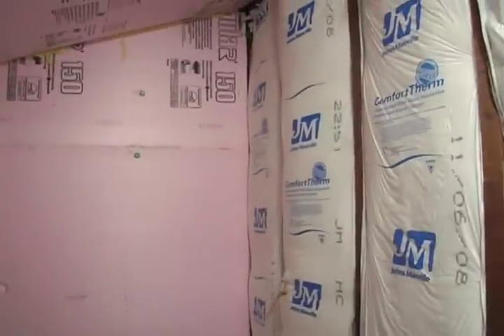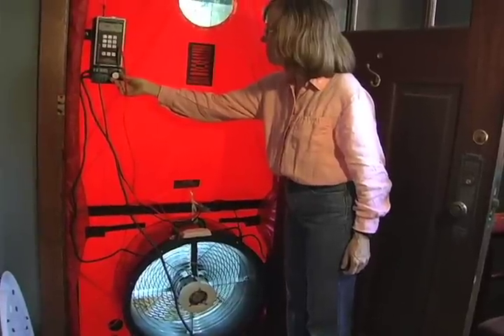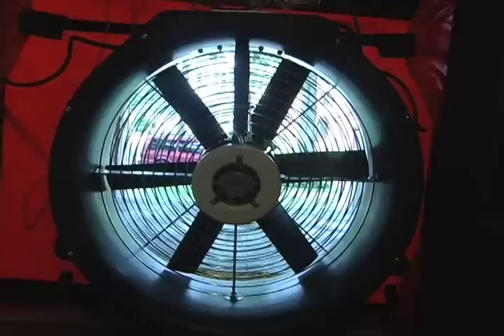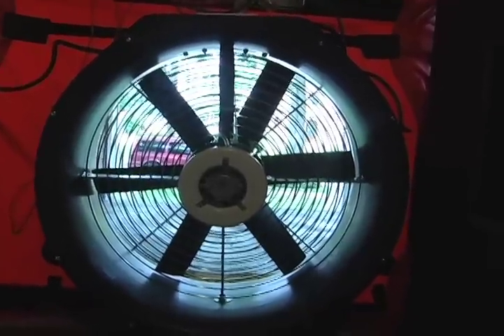In this eZing energy audit, we found a very leaky house with an inconsistent insulation strategy, despite substantial work by the previous owners. Using the blower door airflow measurements, we calculated the natural air change rate per hour for a typical winter or summer day. We found that in this house it was over 1, meaning that over 100% of the conditioned air in the house is being lost every hour.